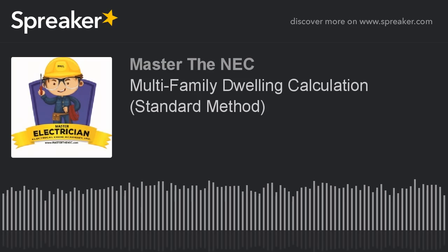Now, the portion that we have above 200 is 289 amps. I can take that 289 amps and apply a demand factor of 70%. So, that's 289 times 70% or 0.70, depending on your calculator. That equals 202 amperes. So I add 200 and 202 amperes together, and now I have 402 amperes of calculated neutral load. That is my calculated neutral load. Okay? So that's how I come up with that, and I have to have a conductor that can at least handle this load. All right?